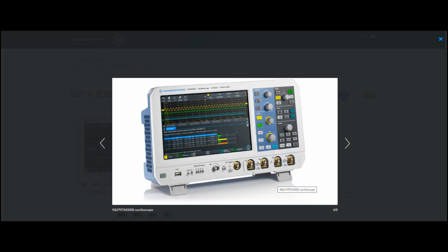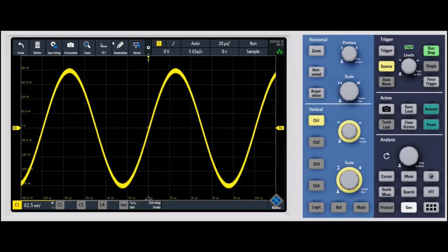This is a pretty nice capability and something that's common across our 3000, 4000, on into our Windows-based scopes like the RTE, RTO, RTP. And in almost all cases, the probes can actually be used across those different product families, particularly for general purpose probes like high voltage probes, current probes, those types of things. So let's go ahead and dive into the probe interface itself.